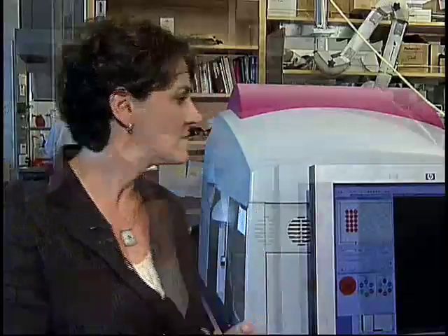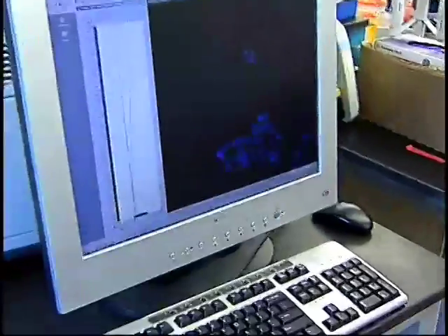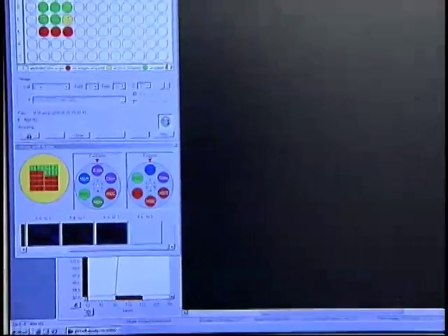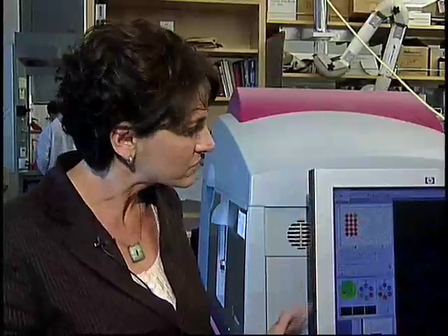So let's get started. So now Kenny, our high content screening expert, is starting the instrumentation, and it's loading the plate in the plate reader. It's setting the objectives, the lenses to 10x objective, the correct filters to detect fluorescence in the blue channel. And now you can see the data are coming up. We're scanning 20 fields per well, see here, and as the data are collected, they're coming up on the screen, and they're also being saved into the computer. They'll go to our database for analysis later.